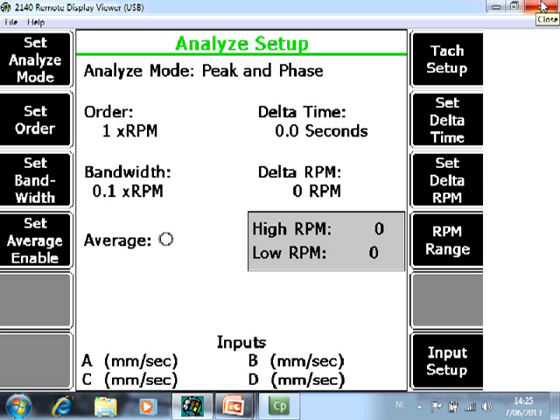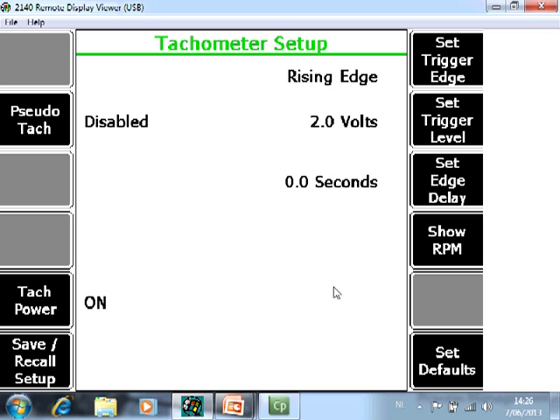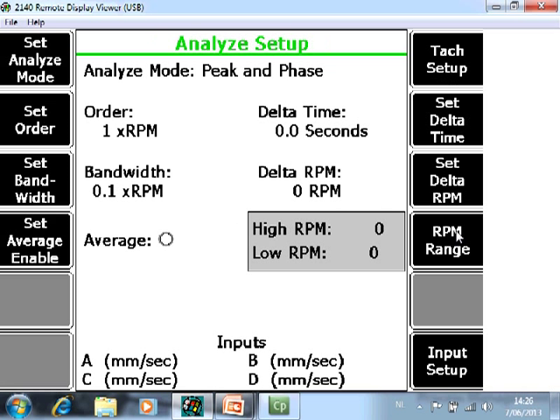Tach Setup F7. Here you can configure your tach. For this tutorial we are using a traditional photo tach. That means that the power has to be on and the trigger level is 2V. You can check immediately if your tach is well installed and configured by pushing F10 Show RPM. As you see the speed information is coming in so the tach is correctly configured.